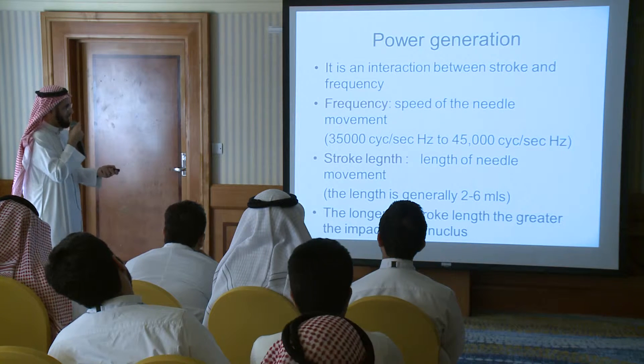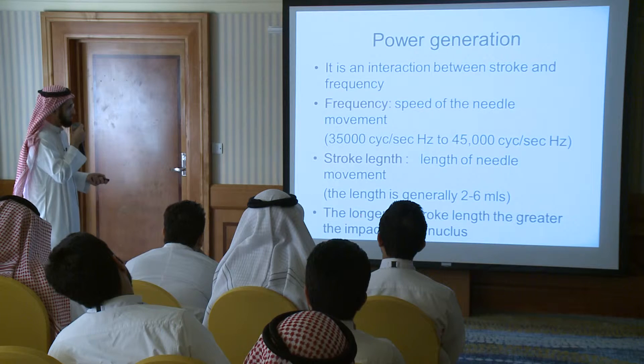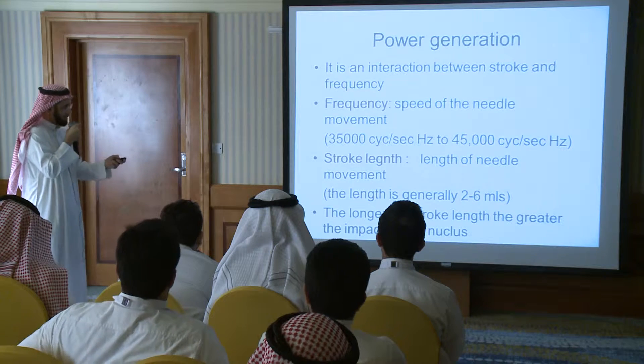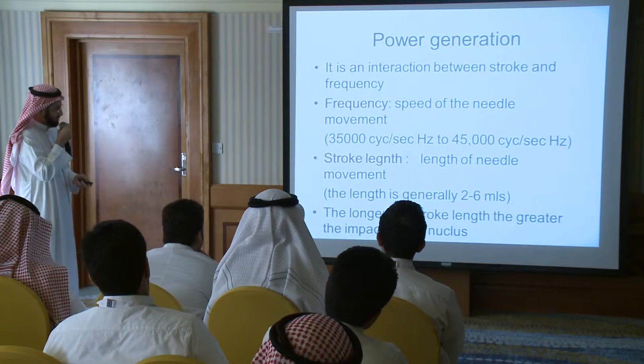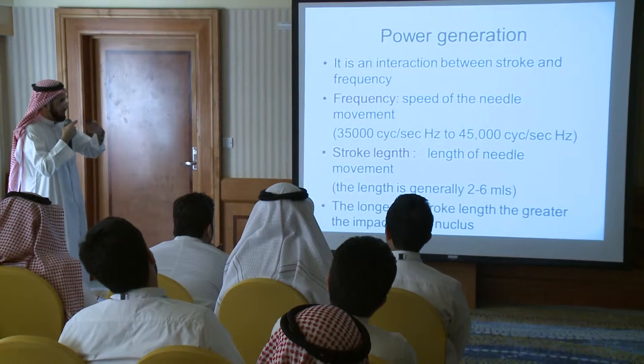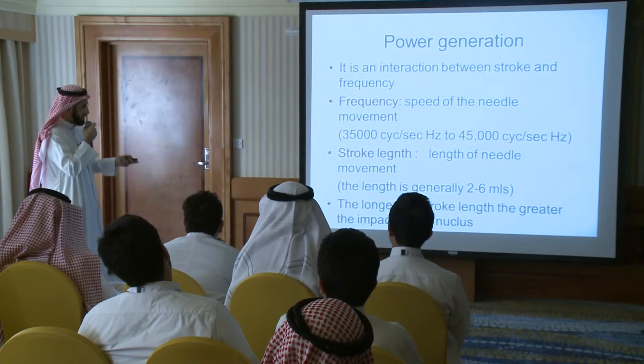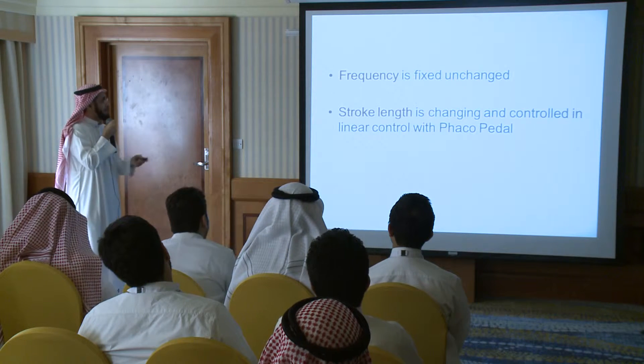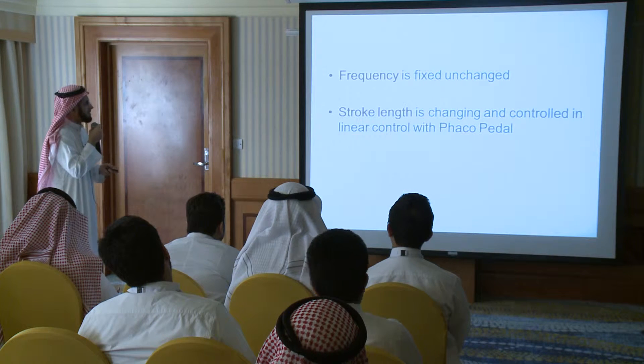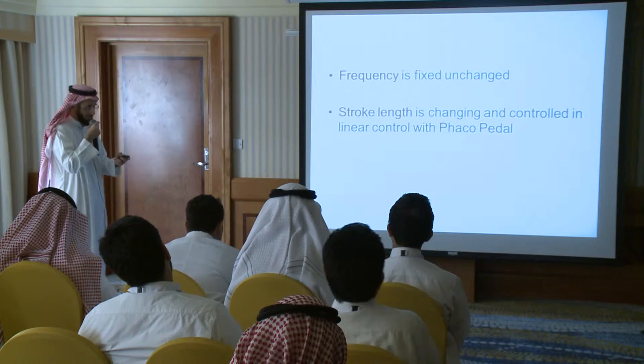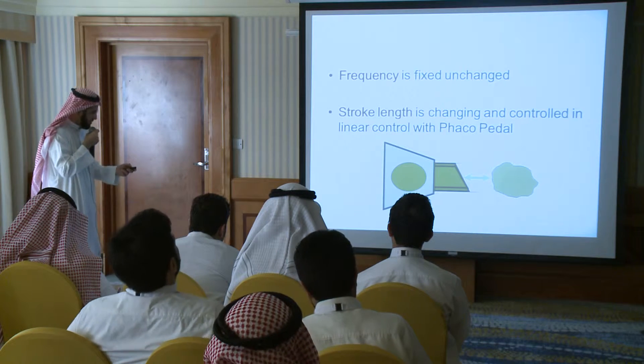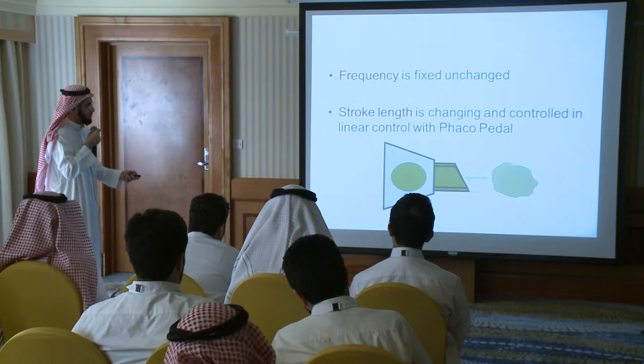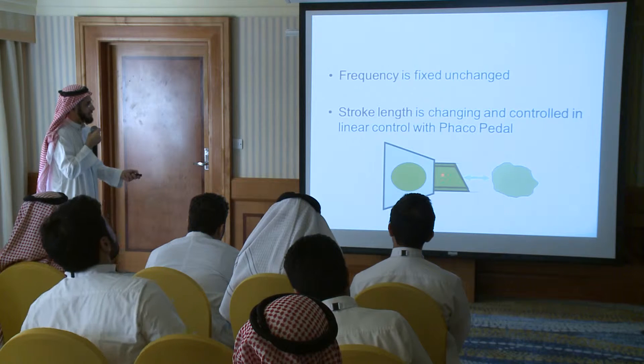You can play with the stroke length and the length of the needle movement. The movement is usually from two to six millimeters. The longer the needle movement while doing the emulsification, the stronger or the more effect you can get. As I said, the frequency is stable — it's not changing — but we can change the stroke length according to the energy that you need. This is what we mean by the stroke: the forward and backward movement of the phaco needle, ranging from two to six millimeters.